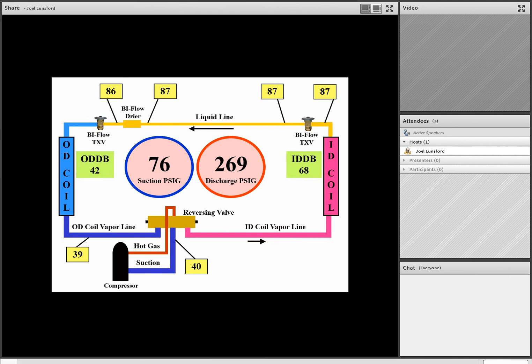Suction pressure is low. Discharge pressure is low. All the temperatures around the refrigeration circuit, as far as the liquid line and so on, that all looks fine. There's nothing jumping out as far as a kinked liquid line or anything like that. But what condition, let me ask everyone, what condition would give us high superheat, starved outdoor coil, low subcooling, starved indoor coil in the heating mode, low suction pressure and low discharge pressure? In other words, 2 starved coils and both pressures are low. How about a low charge that we just happen to pick up in the heating mode of operation? Low charge, classic low charge, 2 starved coils, and both pressures are low.